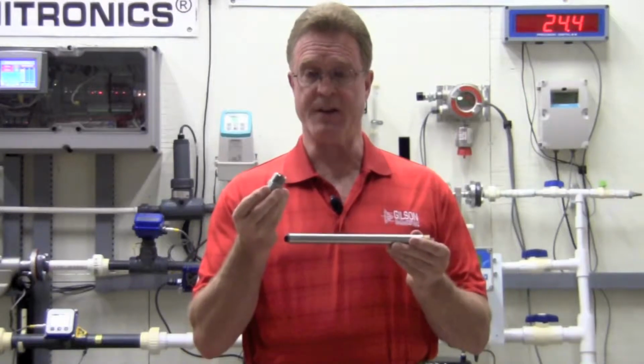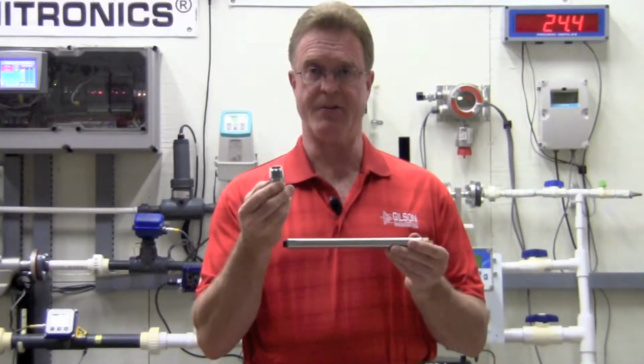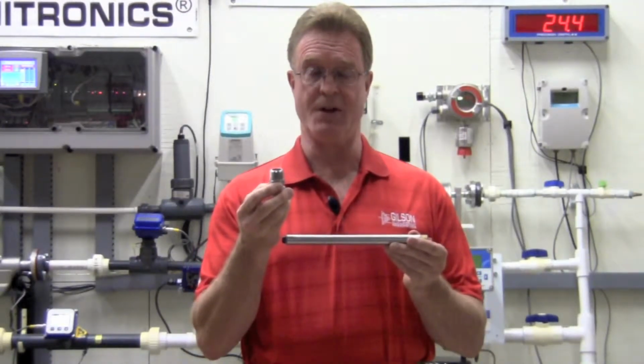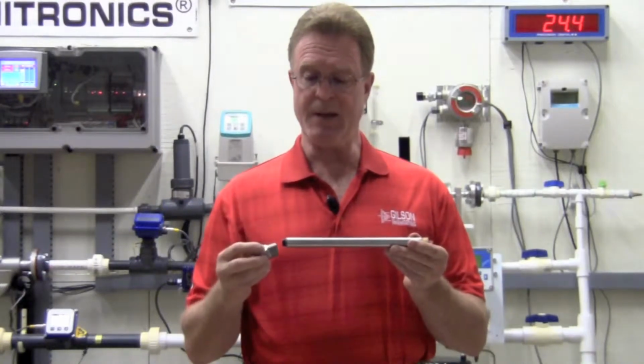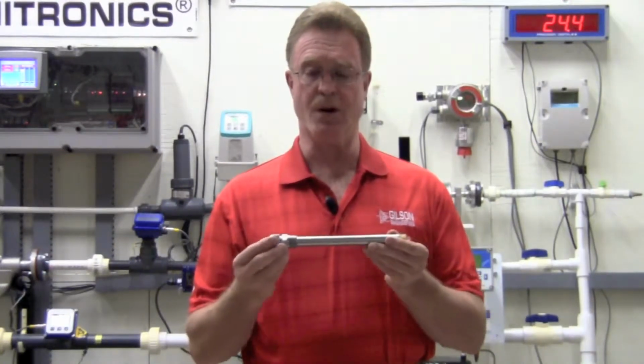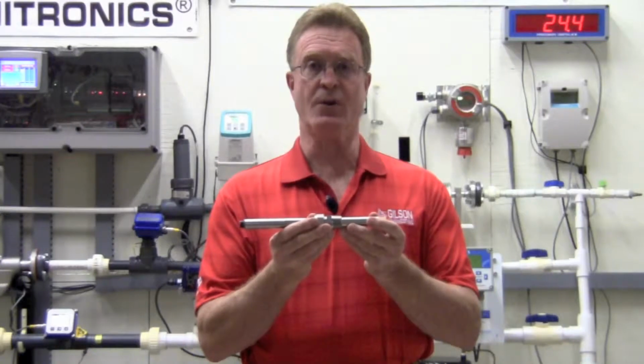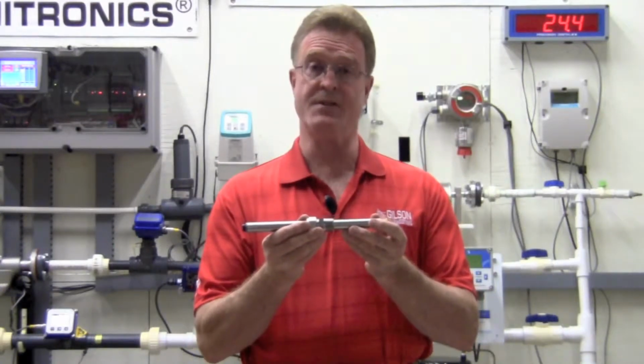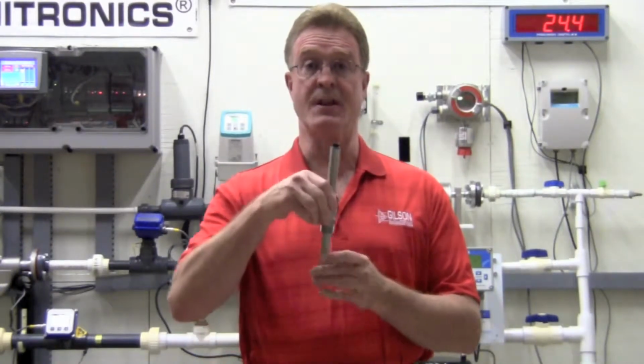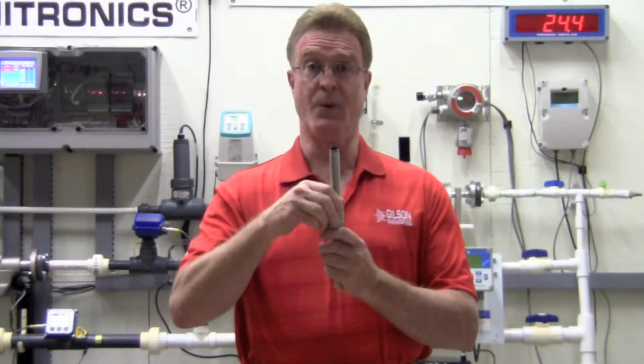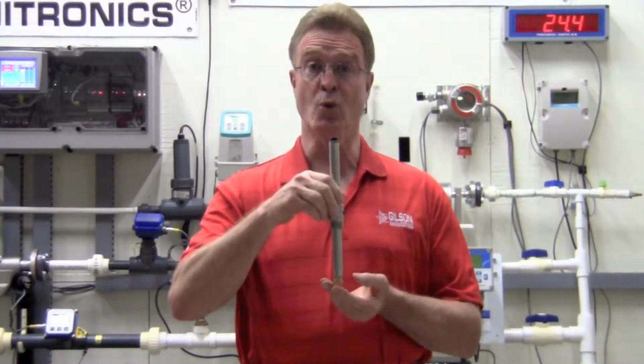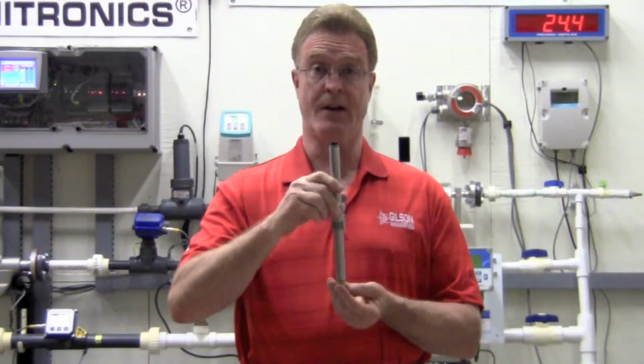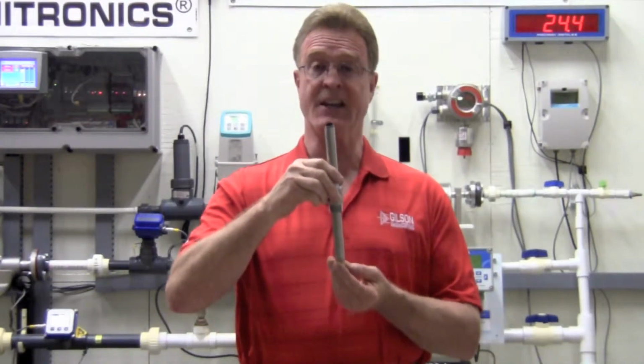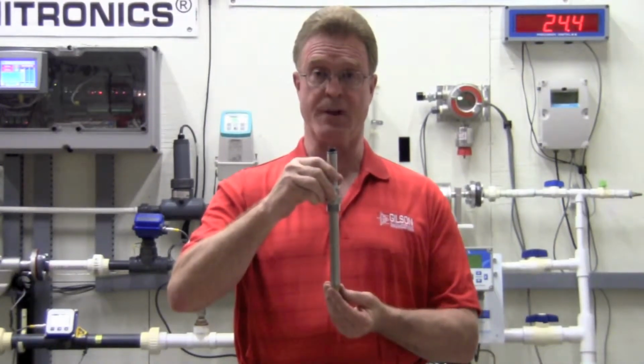We have a compression fitting. This one I happen to have here has a 3/4 inch NPT process connection. It may be installed onto the S10 probe so that the 3/4 inch NPT threads face the process. And we use this in an immersion style so that if I were to go across a flume or a weir and have a 3/4 inch connection, I can lower the probe down into the flow stream.